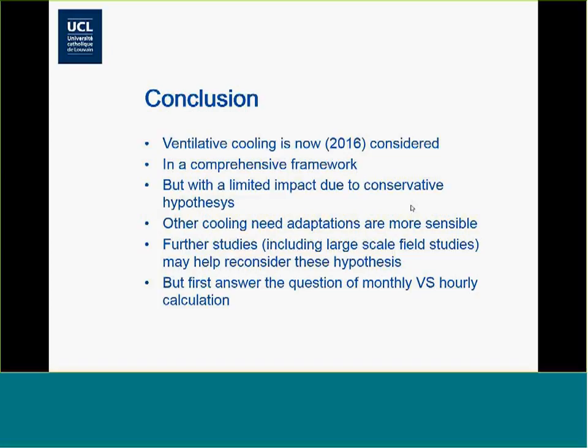But further, before trying to calculate more precisely the fraction of time of use, for example on a monthly basis, there's a key question that should be asked: is it consistent to have a monthly calculation rather than an hourly one regarding cooling? Because you all know, I guess, the impact of thermal mass and the impact of the dynamic response of the building for cooling loads is very, very important, much more important in our climate than for heating, for example. Basically, in heating, it's always cold, and you just have a little bit of sun to reduce your losses. But for cooling, you're in a steady equilibrium between gains and losses. So the dynamic response really is a key factor, and having a monthly based calculation is not very accurate.